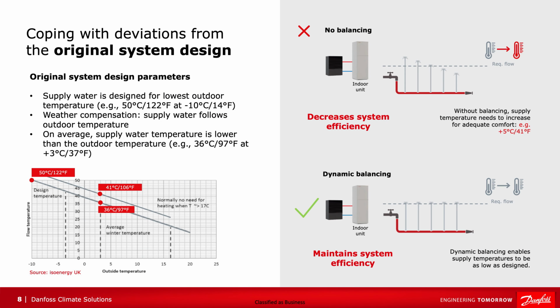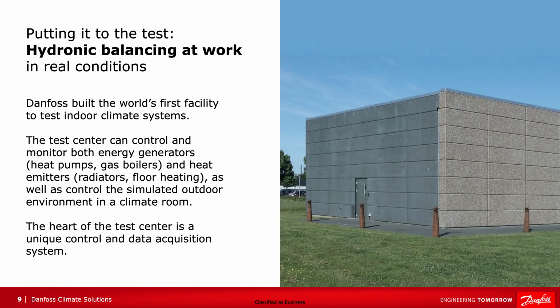With dynamic balancing, in real world conditions, as you can see here, at that part load condition, the flow and the pressure are going to be met, at the same time reducing our flow requirements at the site. How did we know this? How did we prove it? We have the world's first facility to test indoor climate systems. This test center can control and monitor both energy generators, so heat pumps and gas boilers, and heat emitters as well, such as radiators and floor heating, basically simulating the entire condition that you would have in a residential or multifamily commercial building. The heart of the test center, the secret sauce, is the control system of the hydronic system and the data acquisition system.